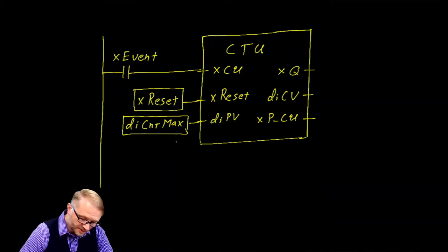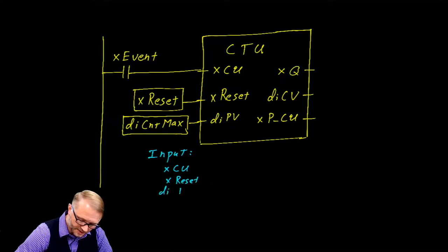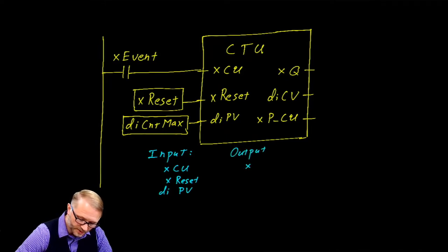To better understand this counter, let's put it into that structure that we've been using throughout class. We have our inputs as a boolean count up, a boolean reset, a double integer called programmed value. On the outputs, we have a boolean Q, a double integer current value, and a boolean — the previous value of count up.